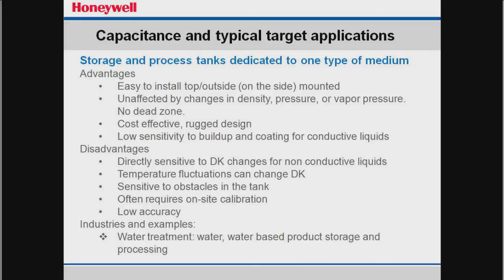The disadvantage is that they're directly sensitive to changes in the dielectric constant. So when you're making this measurement, you're assuming that this material has a certain dielectric constant, and it's not going to change, because if the dielectric constant changes, all bets are off. And it could change with temperature. So temperature fluctuations can change the dielectric constant, and that will affect the reading.